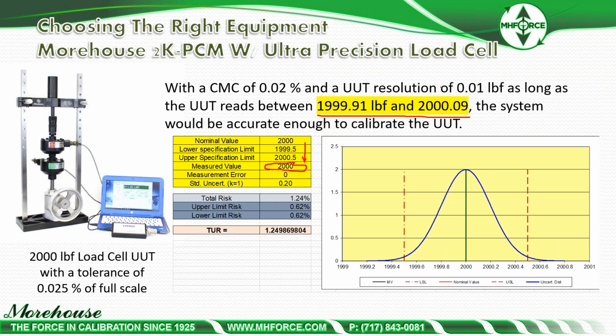So that's a big difference from being able to swing the door open. I can go all over the curve and have lots of room to say something's in, compared to having very little room in this scenario. In all scenarios you can use the device. It's just that as the accuracy requirements get greater, with a tolerance of 0.025% of full scale, you need to be that much more critical on the location of the measurement to call the device in tolerance.